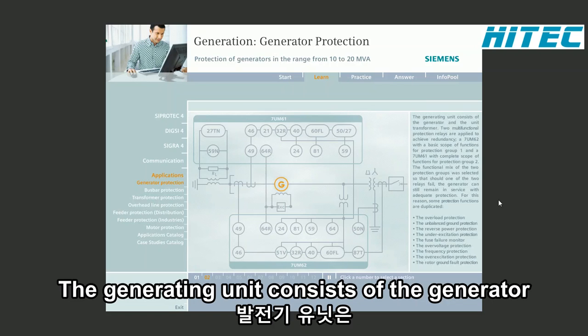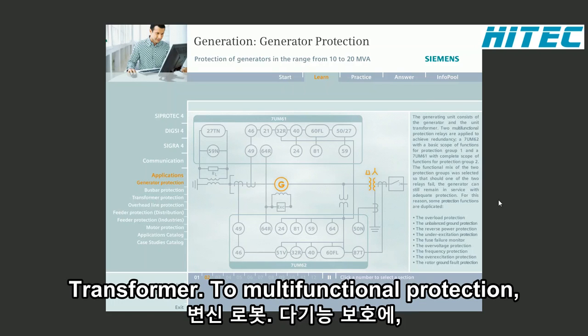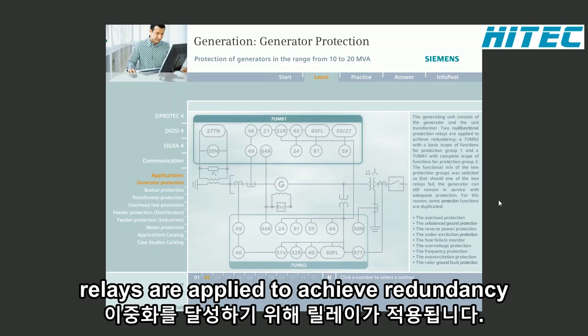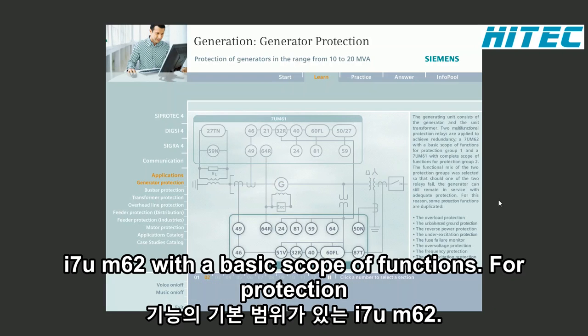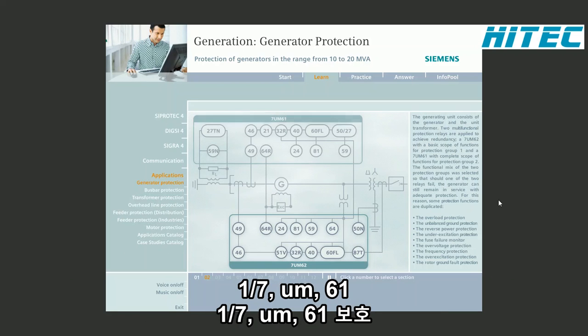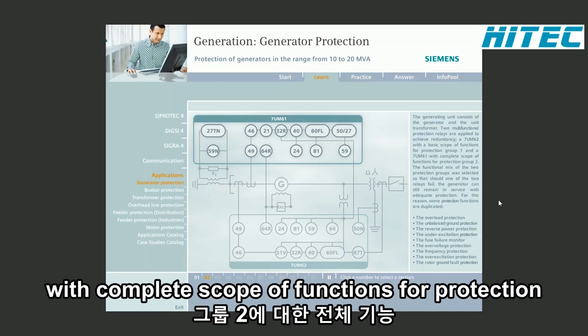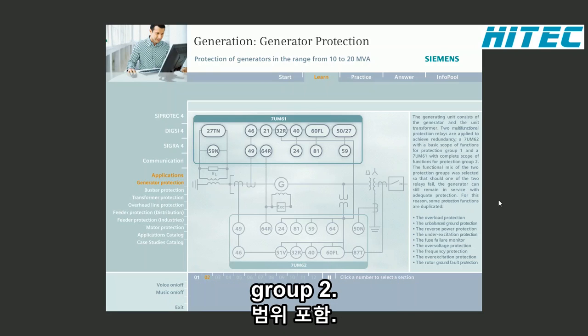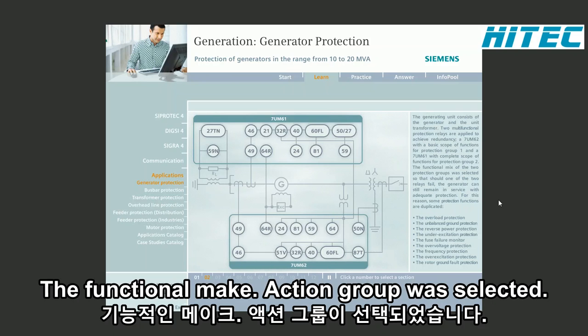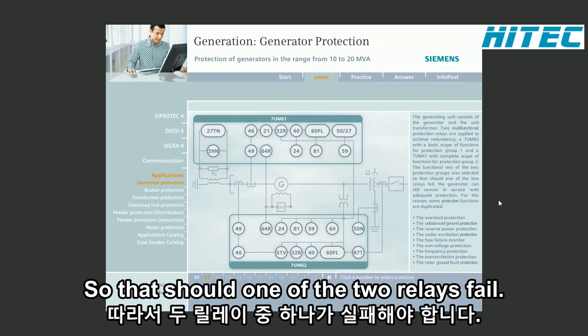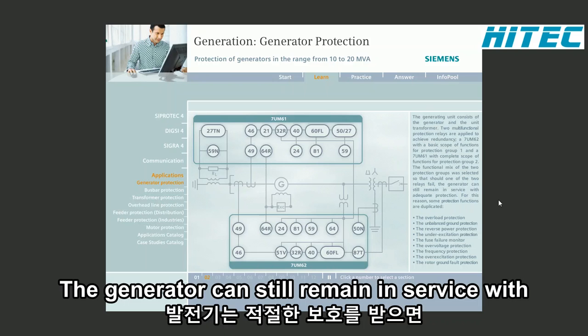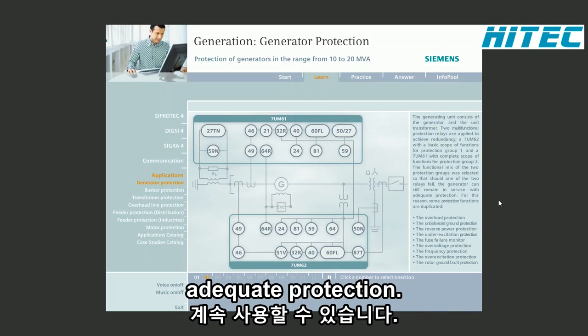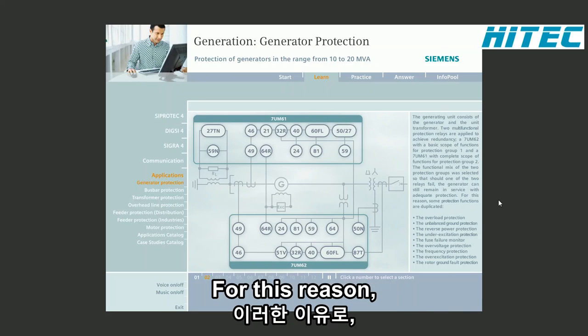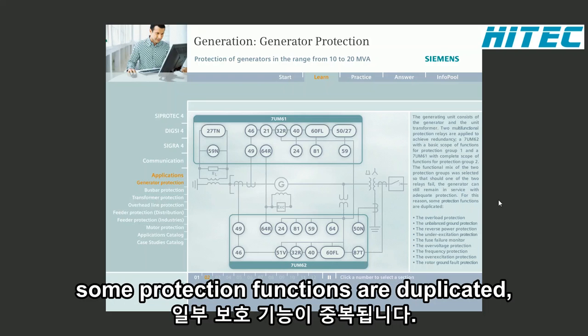The generating unit consists of the generator and the unit transformer. Two multifunctional protection relays are applied to achieve redundancy. A 7UM61 with a basic scope of functions for protection group 1, and a 7UM62 with complete scope of functions for protection group 2. The functional mix of the two protection groups was selected so that should one of the two relays fail, the generator can still remain in service with adequate protection. For this reason, some protection functions are duplicated.